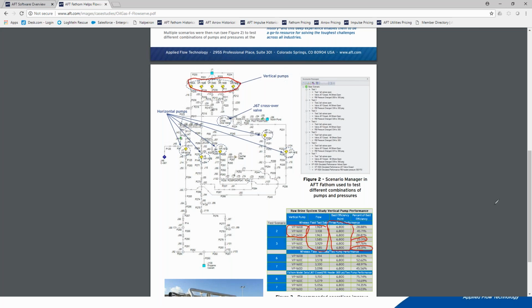Well, when Flowserve kept going along with this study, they started by turning off various pumps and only running maybe 2 pumps at a time. And when they run only 2 pumps at a time, they would also close off some of these cross-tie valves to eliminate some of that resistance. What they found was they were able to get some dramatic increases in their flow. And so rather than having 3 pumps running, they only ran 2 pumps and they got additional flow. And it was much closer to the flow that they actually needed.